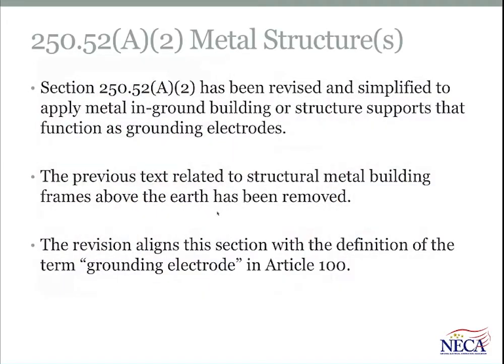Moving into grounding, Article 250 provides the rules for grounding and bonding. And the first change we talk about here today is in 250.52A. That's the details and descriptions of electrodes that are permitted for services and systems. And Panel 5 acted not so favorably to recognizing metal in-ground. I'm getting ahead of myself here.